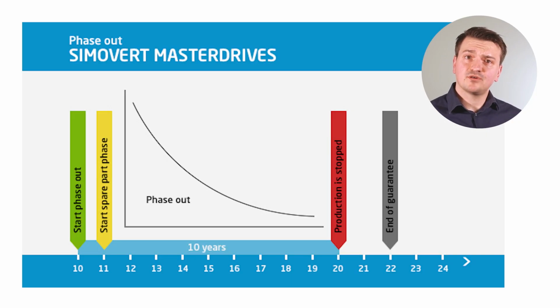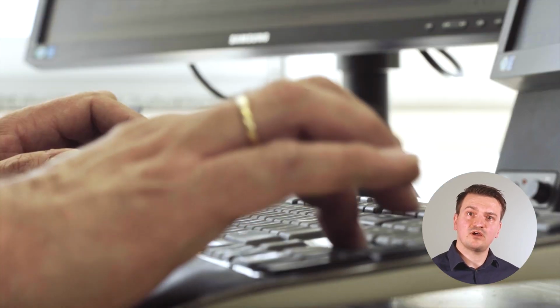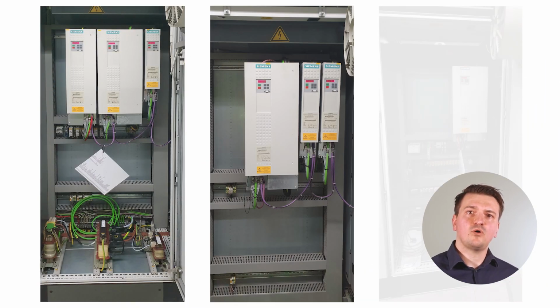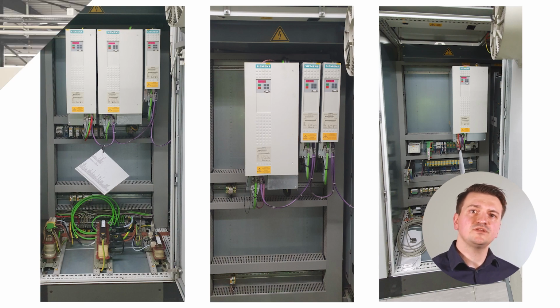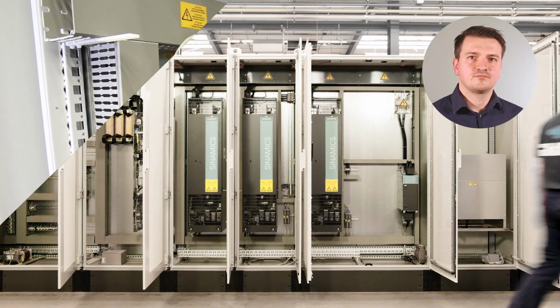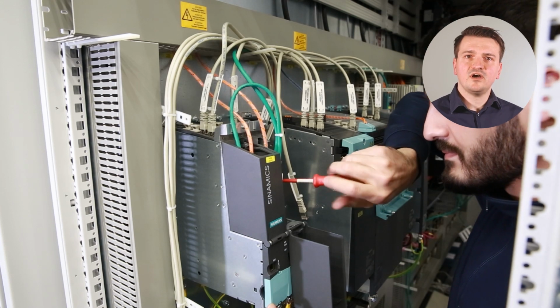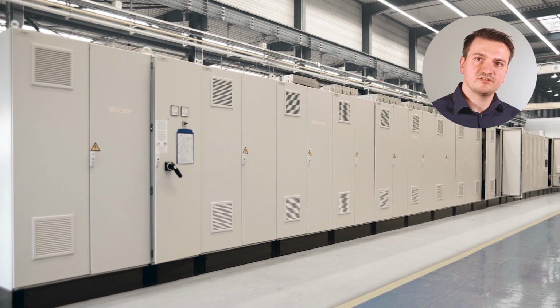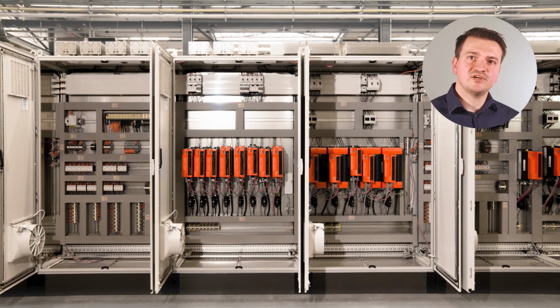We already discussed the topic of discontinued products and services. This also has a strong impact on the drive technology of a plant. Here is an example. Siemens already initiated the product phase-out of the Master Drive series on October the 1st, 2010. After a phase-out period of 10 years, production of the Master Drive series was discontinued in 2020. This makes it necessary to upgrade the existing drive technology. In the course of the modification, the old Master Drive control cabinets are replaced by new drive cabinets with Siemens Sinamics modules. We know that each of our customers has their own idea of how they want to achieve their goals in this regard. That is why it is so important to offer customized solutions.